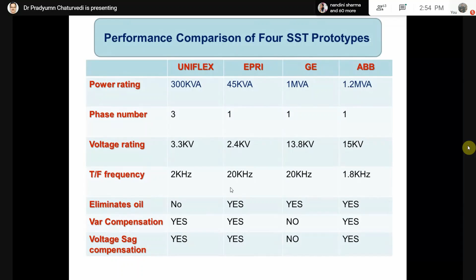So these are a few companies developing SST: Uniflex, EPRI, GE, and ABB, at different voltage ratings. And for operating frequency of the transformer, they only went up to 20 kilohertz, because a problem occurs if you increase the frequency of the voltage given to the transformer, then the power handling capacity will be reduced. So you cannot go beyond this for high power ratings. This is the major issue.